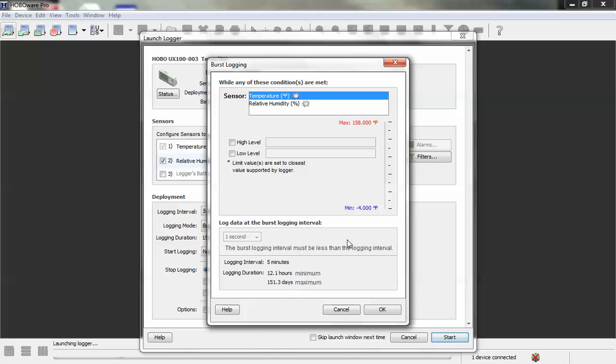Burst logging is based on exceedance of a preset threshold. So what that means is, for example, if we wanted to log at a faster rate based on a specific either temperature or relative humidity threshold, we set that here.